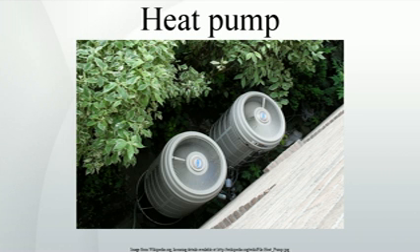This has dual advantage: it functions as a low running cost for air cooling, and, if groundwater is relatively stagnant, it cranks up the temperature of the ground source, which improves the energy efficiency of the heat pump system by roughly 4% for each degree in temperature rise of the ground source.